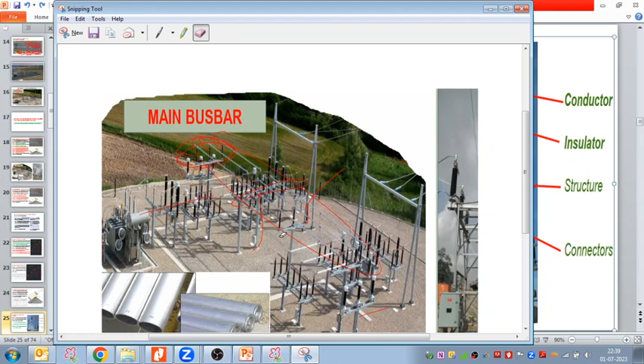So for each phase, we usually plan a separate support structure, with a separate post insulator. If you see in this sketch, here again, one common structure and then three post insulators. That could be 132 kV, but above 132 kV, like 220 kV, 275 kV, 400 kV, we take an individual support structure and an individual post insulator as well.